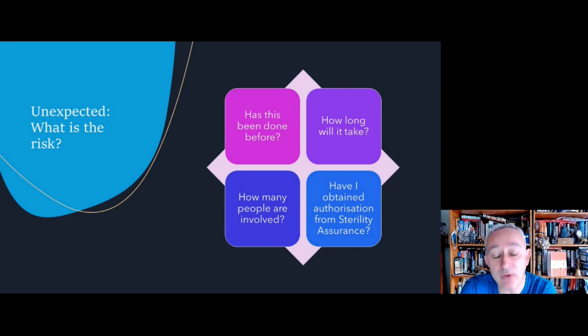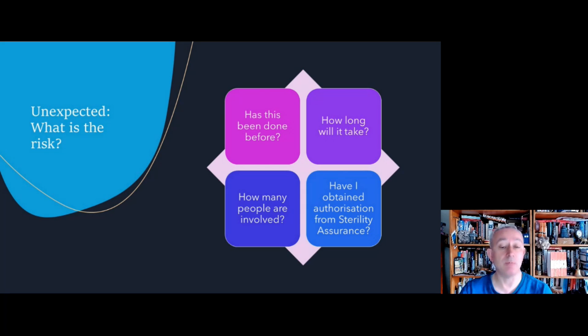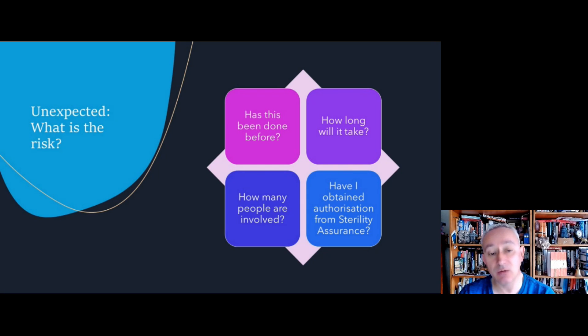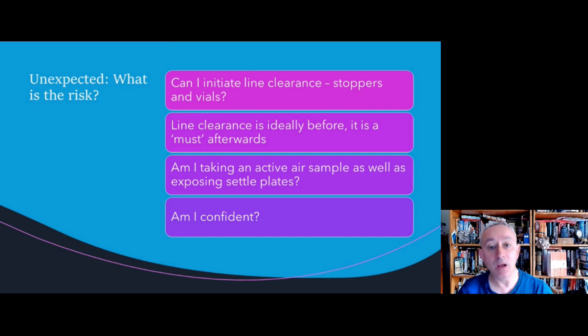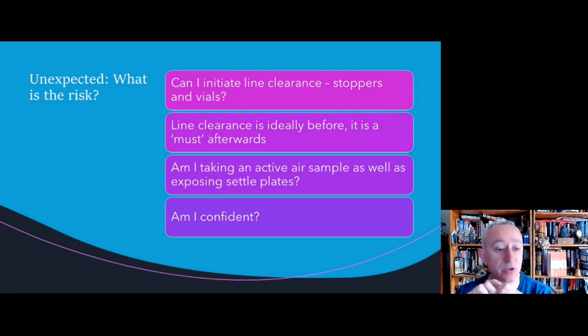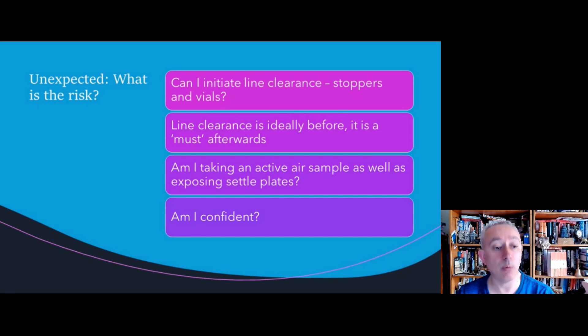When considering whether to carry out an intervention, we need to understand that in reality there may be situations not fully covered by procedures, and unexpected events may require an immediate response. Key decisions include: has it been done before, how long will it take, and how many people are involved. If it's not routine and hasn't been done before, have we obtained authorization in advance from sterility assurance or from microbiology 24/7 if sterility assurance is not available? We also need to consider whether we can initiate line clearance — not just vials but stoppers as well. Ideally, line clearance should be done before the intervention, but if not, it must be done after. If line clearance is not possible, the intervention probably constitutes greater risk.